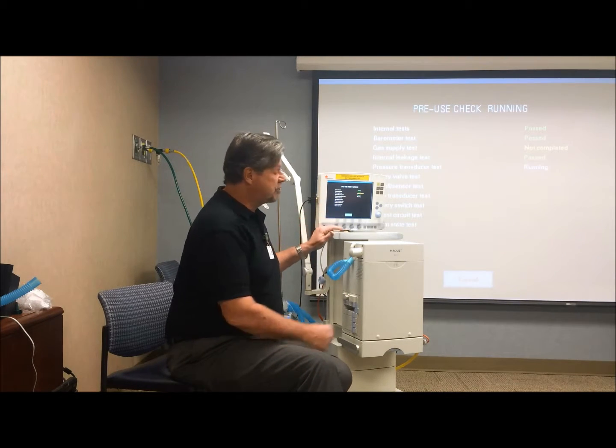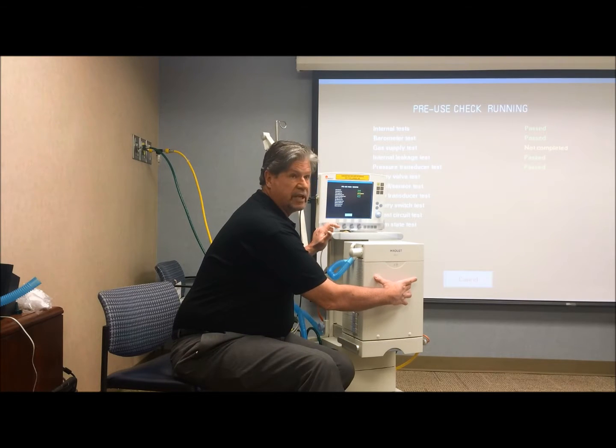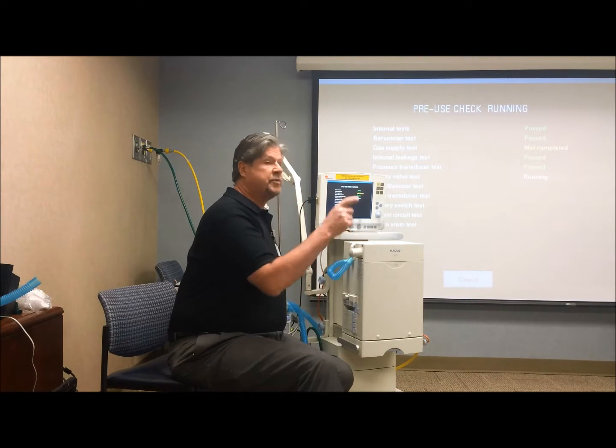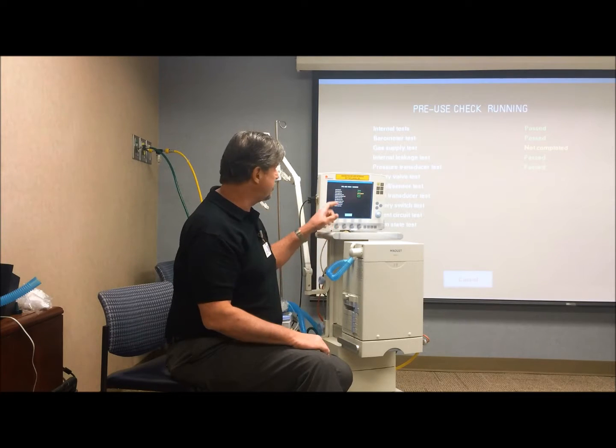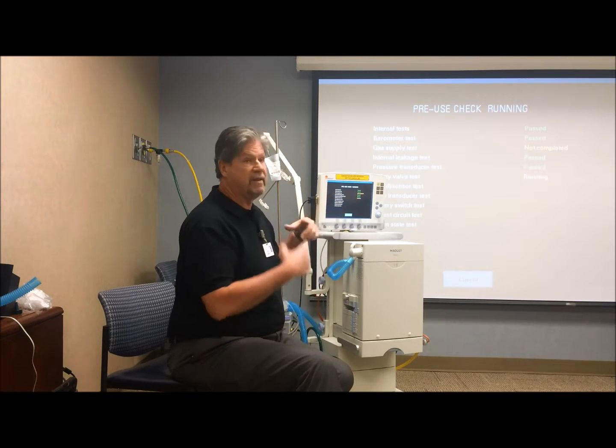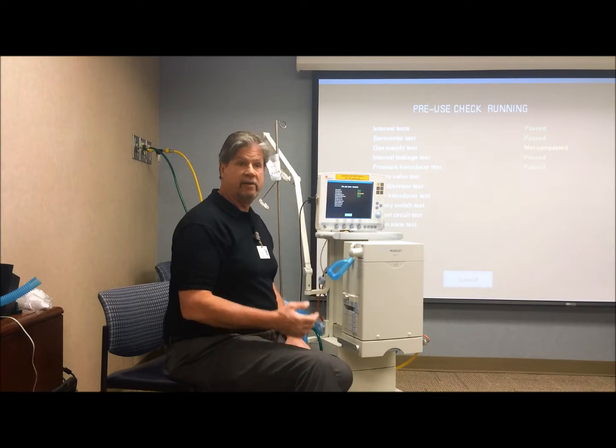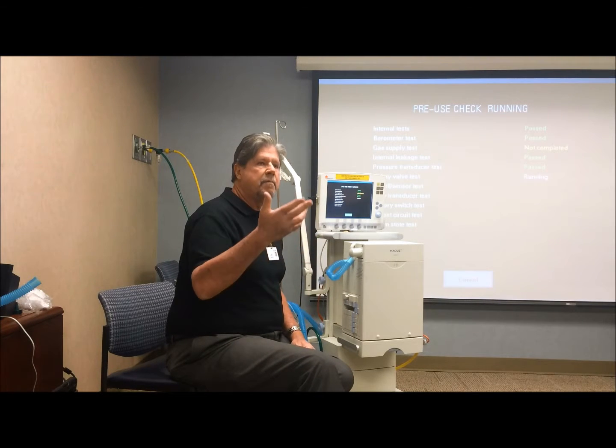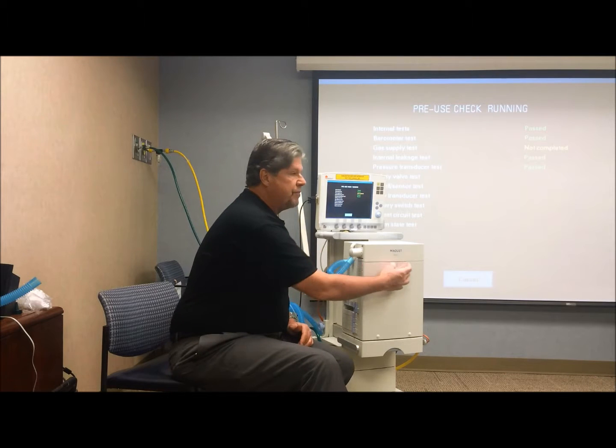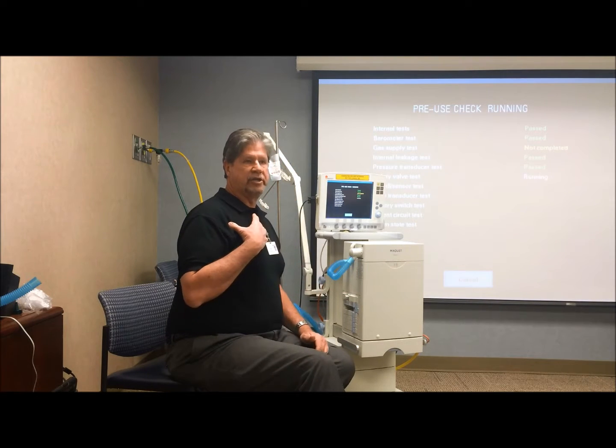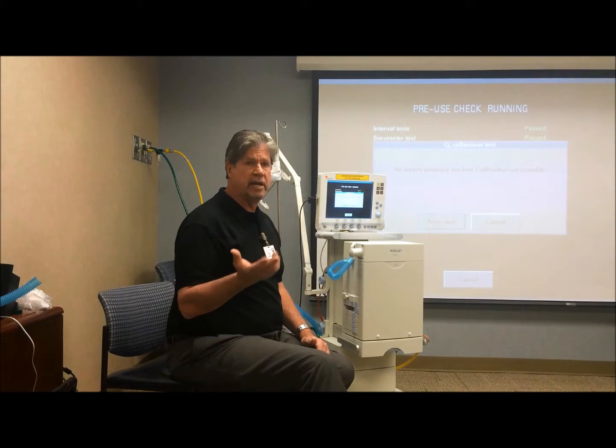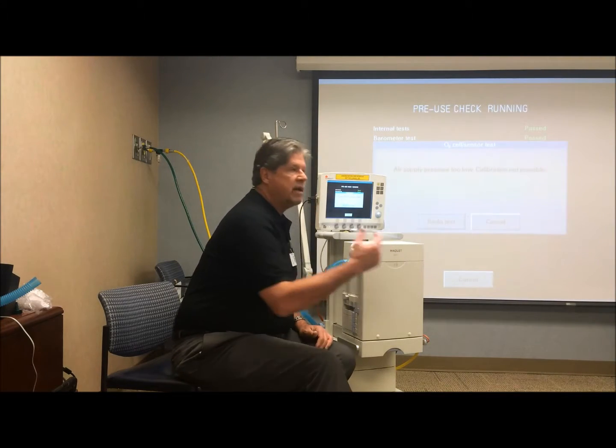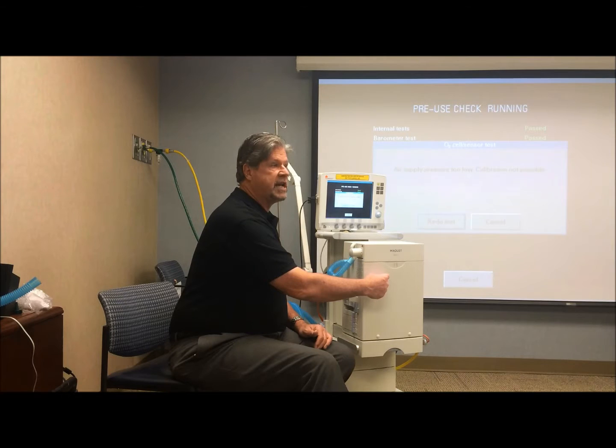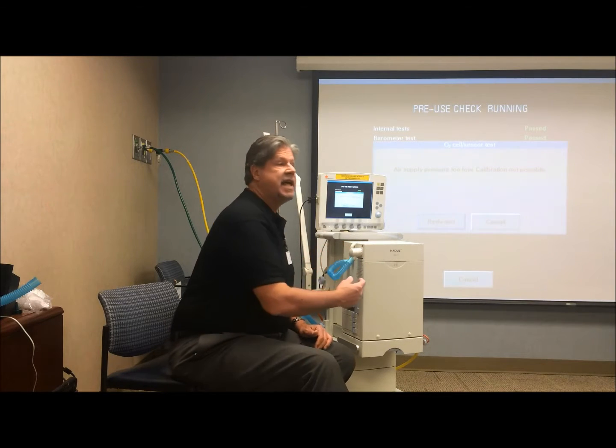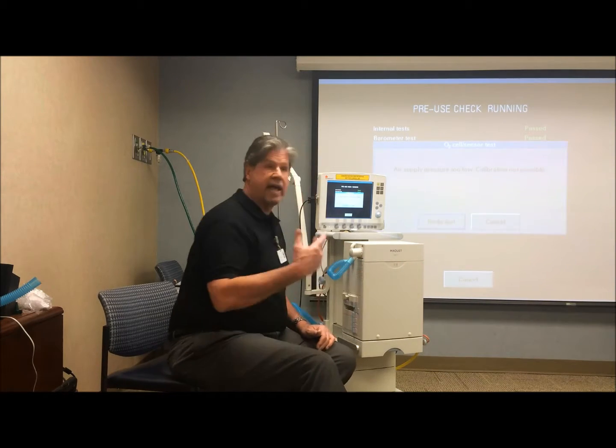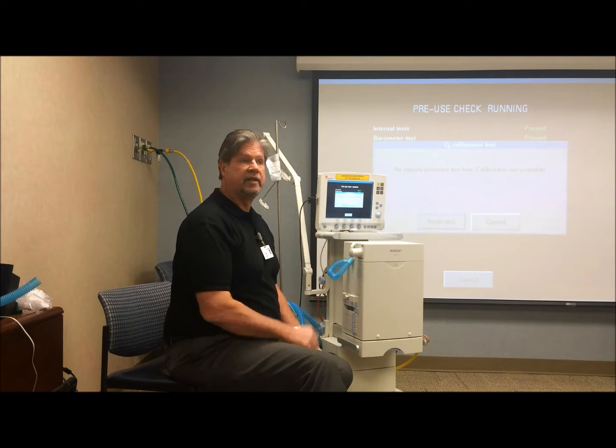The pressure transducer test: there's two pressure transducers that sit on circuit boards in here. There's an inspiratory and an expiratory pressure transducer that it tests, and if that failed, we would know that one or the other failed. Just as a little tidbit, both transducers are the same, so if I were a biomed person and you said the pressure transducer keeps failing, what I can do is take one out of one machine and put it in here, the inspiratory side.